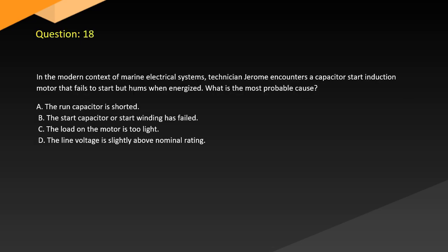Question 18. In a modern context of marine electrical systems, technician Jerome encounters a capacitor start induction motor that fails to start but hums when energized. What is the most probable cause? A. The run capacitor is shorted. B. The start capacitor or start winding has failed. C. The load on the motor is too light. D. The line voltage is slightly above nominal rating.